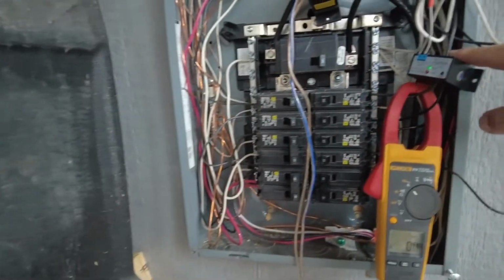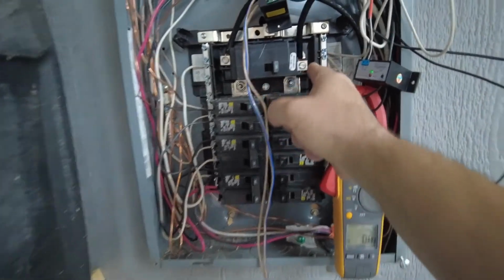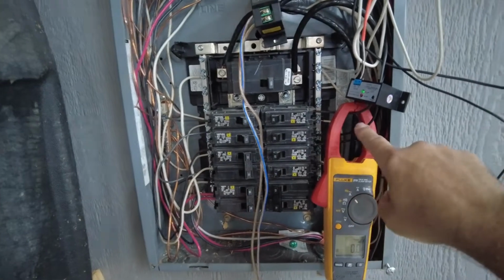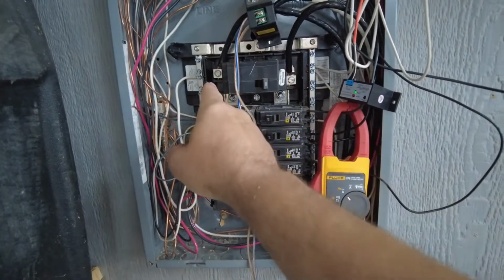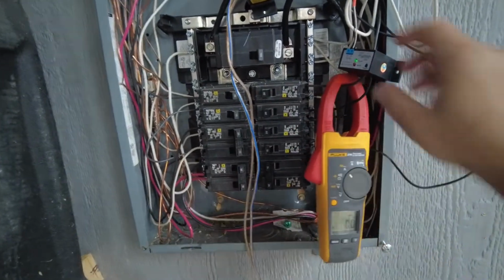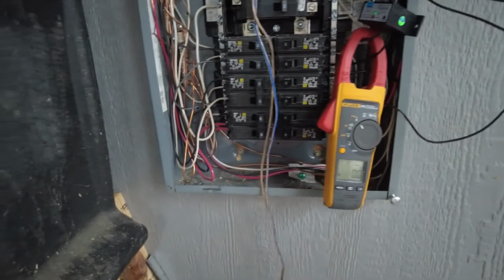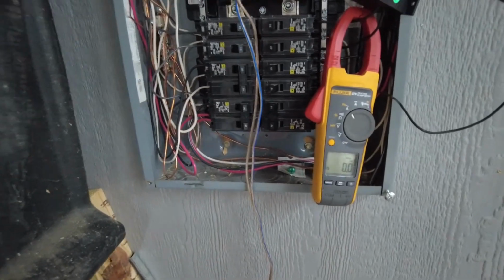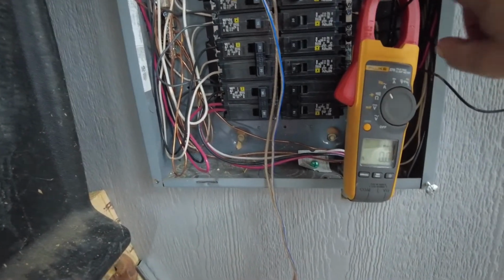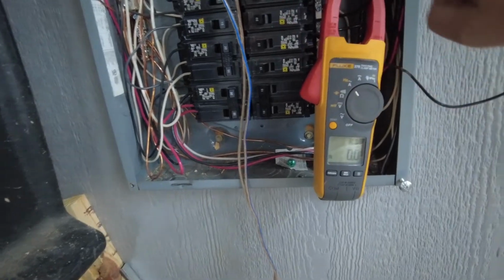Two wires in here will work, but they have to be on the same phase. They would have to be either both on there or both on there. You can't have, like right now, one of these coming from L1, one coming from L2. So they're out of phase of each other. This and your CTs don't understand that. One phase will cancel out the other phase. So this will work, and you can put two wires, same phase. If I use this breaker and that breaker, it would work. So keep that in mind when you use these things.